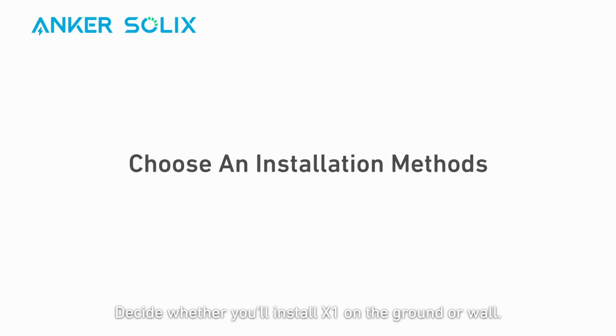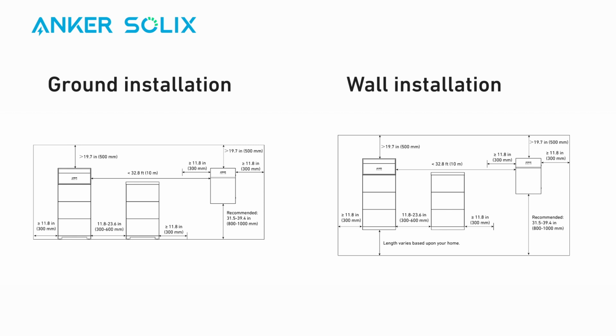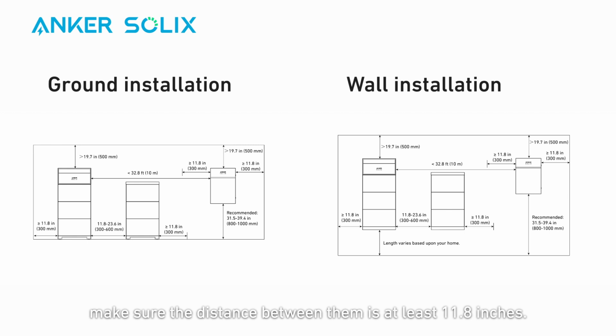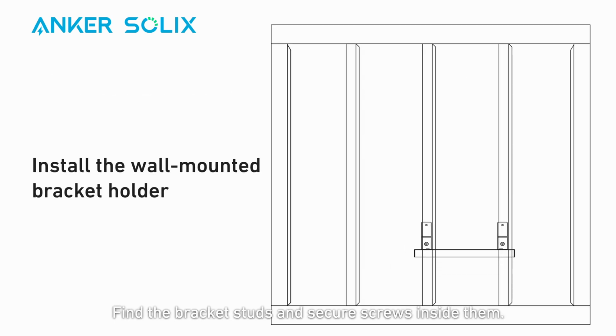Decide whether you'll install X1 on the ground or wall. We'll show wall installation now. Before installing, find a suitable location. Take note of the clearance space needed to keep X1 away from nearby objects. If you need to install more than 2 power modules, make sure the distance between them is at least 11.8 inches. Find the bracket studs and secure screws inside them.